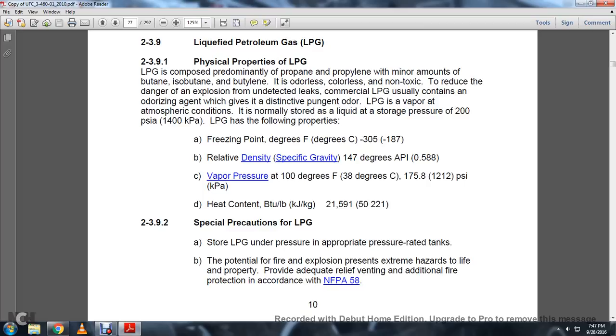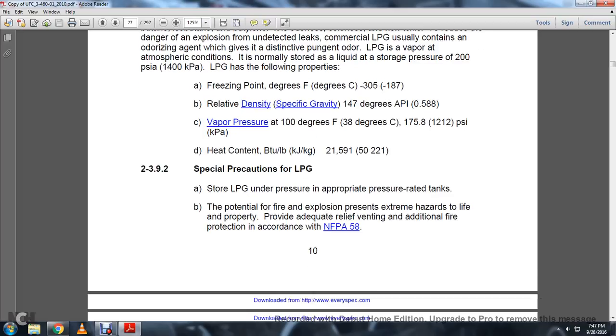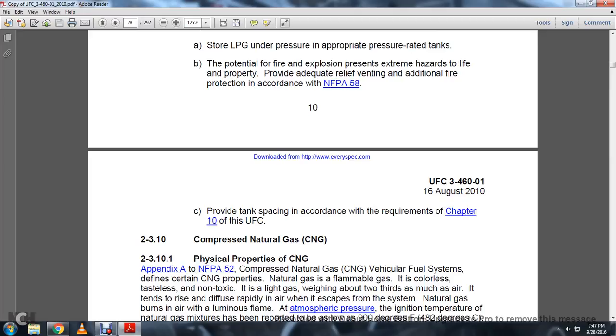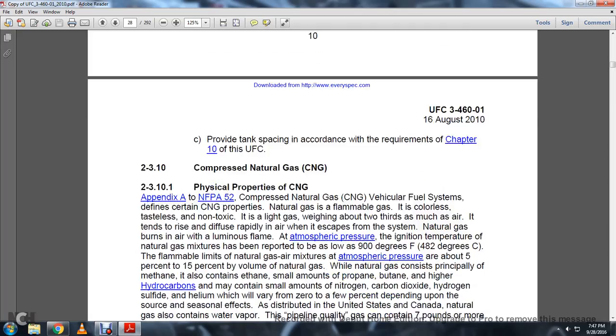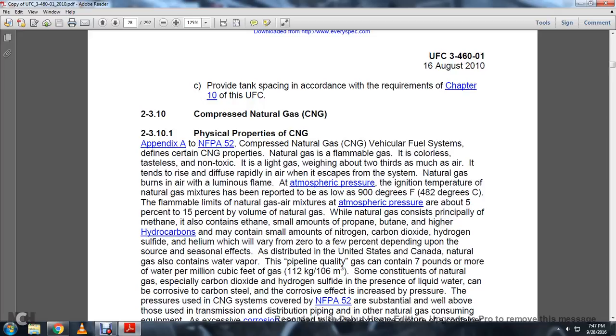2392 special precautions liquid petroleum gas. Store liquid petroleum gas in tanks with the appropriate pressure rating. Potential fire and explosion present an extreme hazard to life and property. Provide adequate relief, venting, and additional fire protection in accordance with NFPA 58. Provide tank spacing in accordance with the requirements of Chapter 10 of this unified criteria.